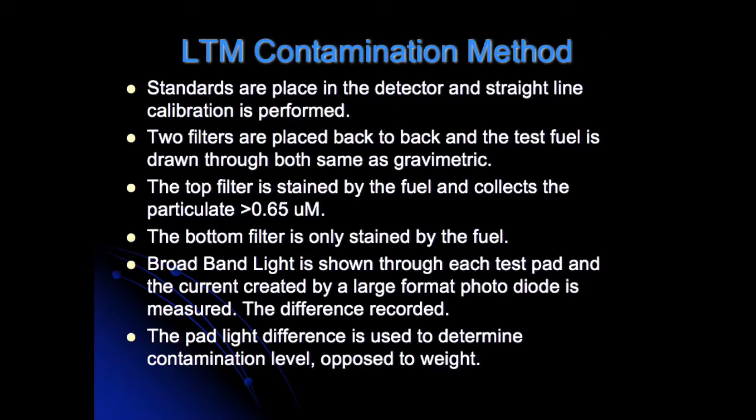D2 Inc. utilizes the light transmission method, LTM, for determining the contamination of fuels. Standards are placed in the detector and a straight line calibration is performed. Two filters are placed back to back and the test fuel is drawn through both, the same as the gravimetric process. The top filter is stained by the fuel and collects particulate greater than 0.65 micrometers. The bottom filter is only stained by the fuel. Broadband light is shown through each test pad and the current created by a large format photo diode is measured. The difference is recorded.